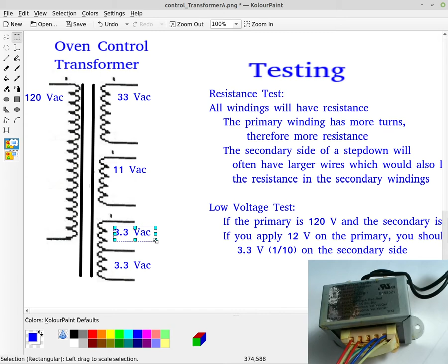So if I give 12 volts on the primary side instead of 120 volts, as designed, I'm only giving it 1/10 of the voltage, since it's designed for 120 volts. I'm just going to apply 12 volts, and I'm going to test these connections. As we test those connections, I would only expect 3.3 volts on the 33 volt winding, 1.1 volt on the 11 volt winding, and 0.33 volts on the very small windings. So let's give this a test and see what we have.